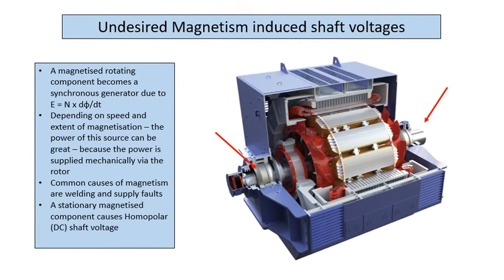Okay, magnetism induced shaft voltage. What typically happens is a drivetrain's maintained, somebody welds on it, and they don't put the earth very close to where the welding's taking place. So you get quite large currents circulating, and you could have, let's say, your shaft underneath in the journal area having a north and a south component. So then you have a north and south spinning with megawatts behind it, and it becomes like a synchronous generator generating into the bearing, and the power is all supplied from the rotor. So it's mechanical power from the rotor. It can be like a gigantic welding machine. And that's how you see this destruction that often occurs.